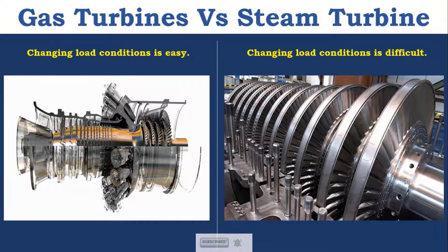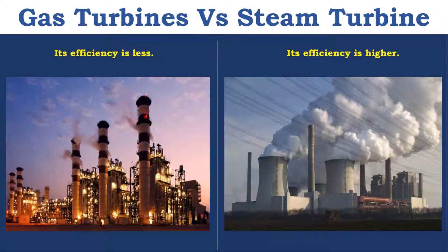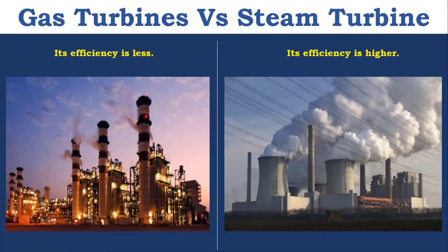Changing load condition is easy in Gas Turbine and difficult in Steam Turbine, because we have to go for governing. By controlling the fuel supply, you can change the load conditions. The efficiency is less in Gas Turbine and more in Steam Turbine, because the power produced by the turbine is used to run the compressor — 70 to 75% of power. Such a case is not there in Steam Turbine. That's why Steam Turbine's efficiency is more compared to Gas Turbine.